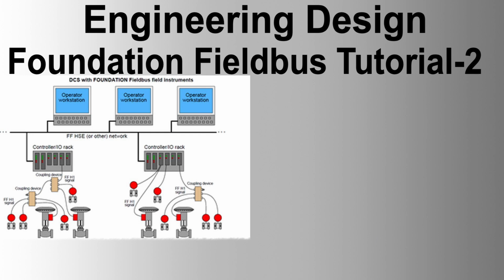Publisher-subscriber model. Publisher-subscriber model is designed to link function blocks. When a publishing function block runs, its output data is stored in the buffer of the publisher VCR. Then the LAS sends CD to the VCR to force it to transfer the data in DT-PDU. Subscriber VCRs receive this PDU and give the data to the subscribing function blocks.